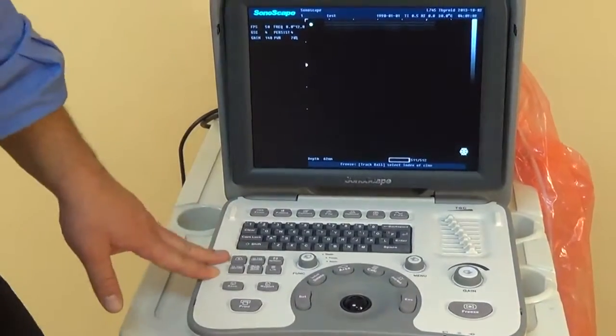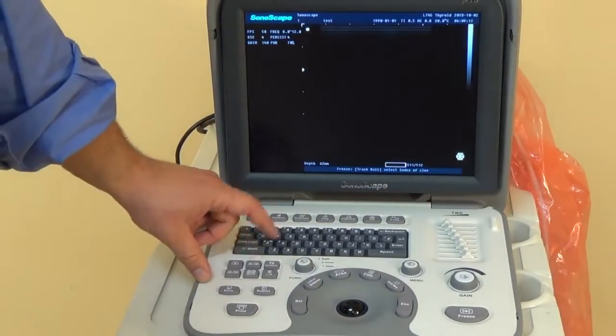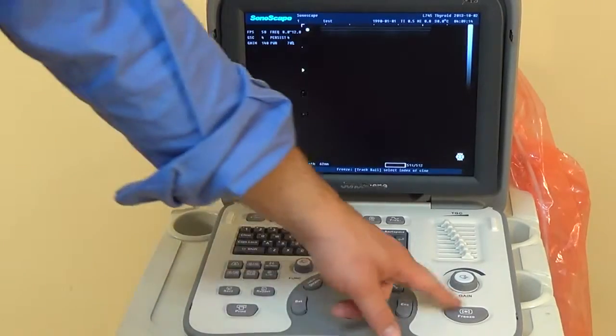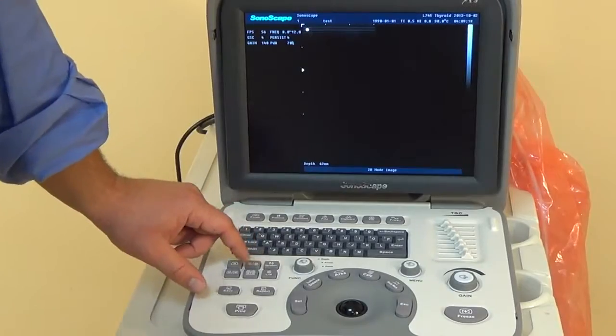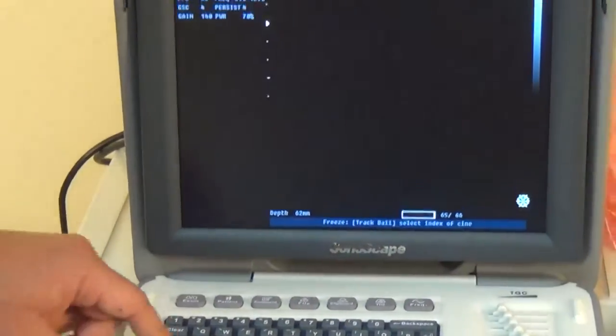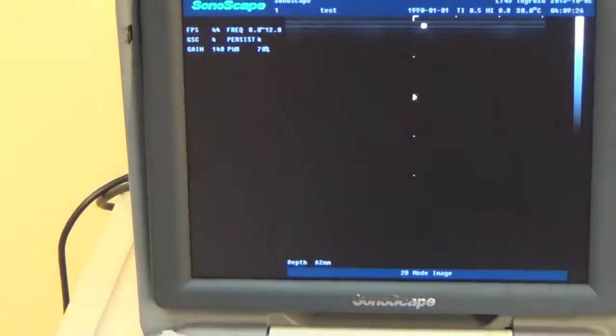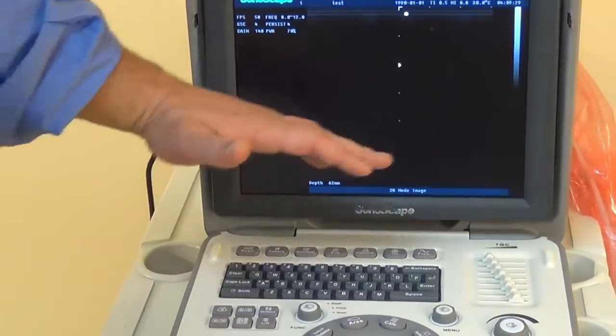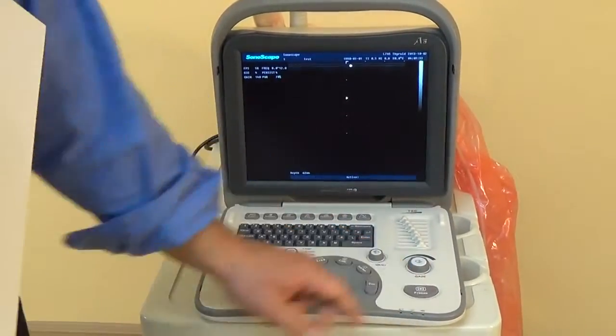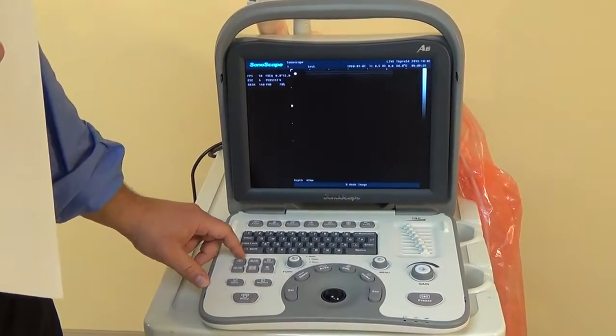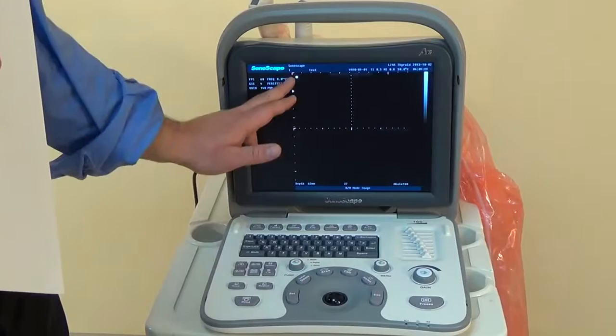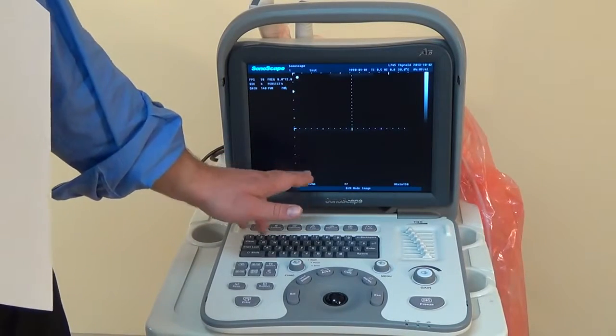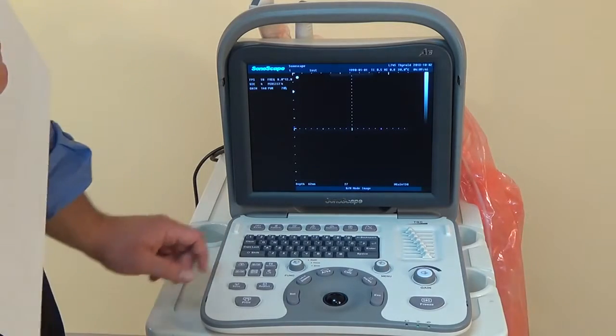On this side, we have our different screens. So B mode is the standard mode that you see. You can have split screen. So if you hit the B slash B, you get one screen. You hit another one, save, and then you get another one, and you can have them side-by-side. So if you're comparing a cyst maybe prior to aspiration or depending on the type of exam you're doing, that's a good feature to have. You can also have a B mode and M mode screen. So you can have your regular image as well as an M mode screen. So if you're measuring a heartbeat, for example, that's pretty much the best use of that screen.